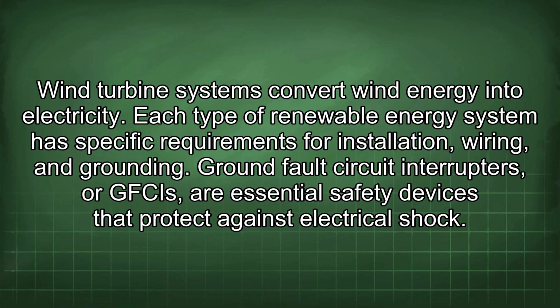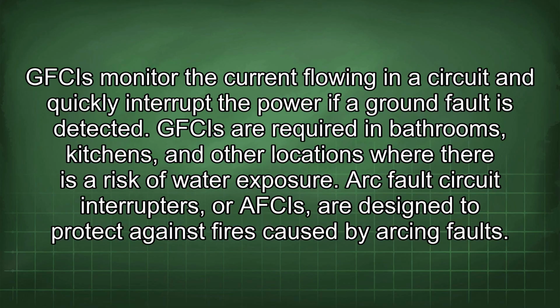Ground fault circuit interrupters, or GFCIs, are essential safety devices that protect against electrical shock. GFCIs monitor the current flowing in a circuit and quickly interrupt the power if a ground fault is detected. GFCIs are required in bathrooms, kitchens, and other locations where there is a risk of water exposure.